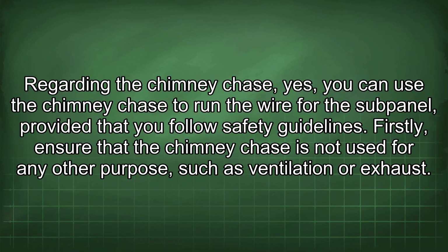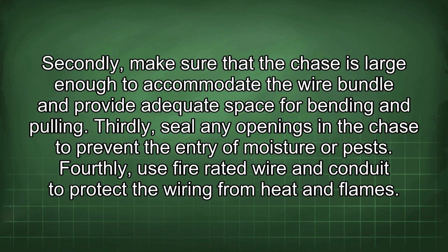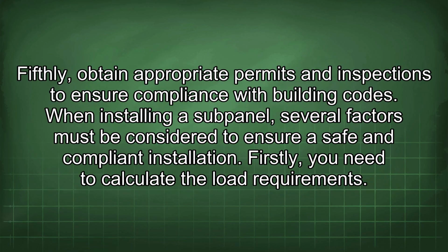Firstly, ensure that the chimney chase is not used for any other purpose, such as ventilation or exhaust. Secondly, make sure that the chase is large enough to accommodate the wire bundle and provide adequate space for bending and pulling. Thirdly, seal any openings in the chase to prevent the entry of moisture or pests. Fourthly, use fire-rated wire and conduit to protect the wiring from heat and flames. Fifthly, obtain appropriate permits and inspections to ensure compliance with building codes.